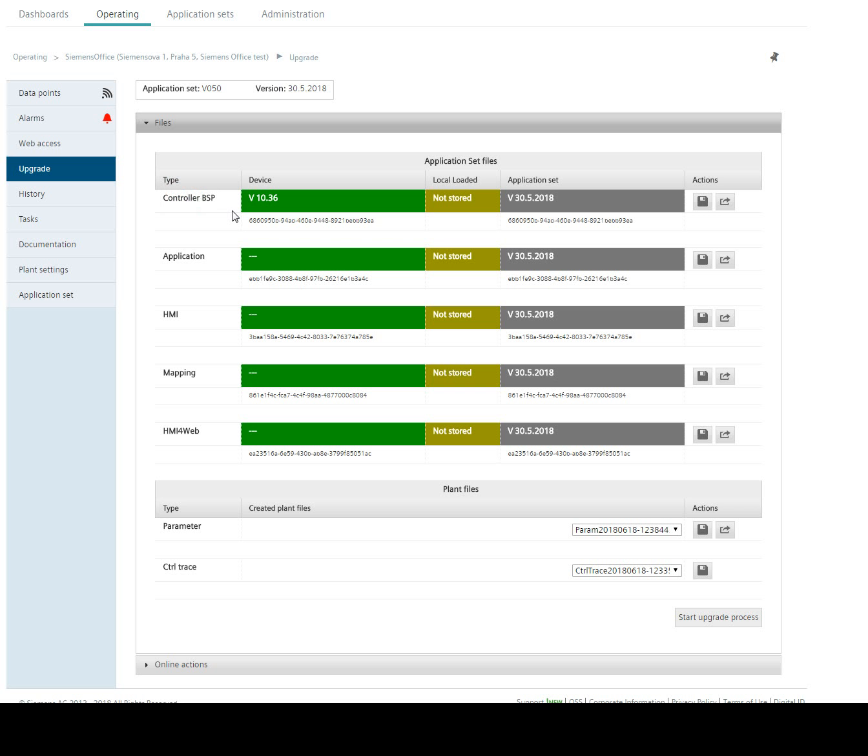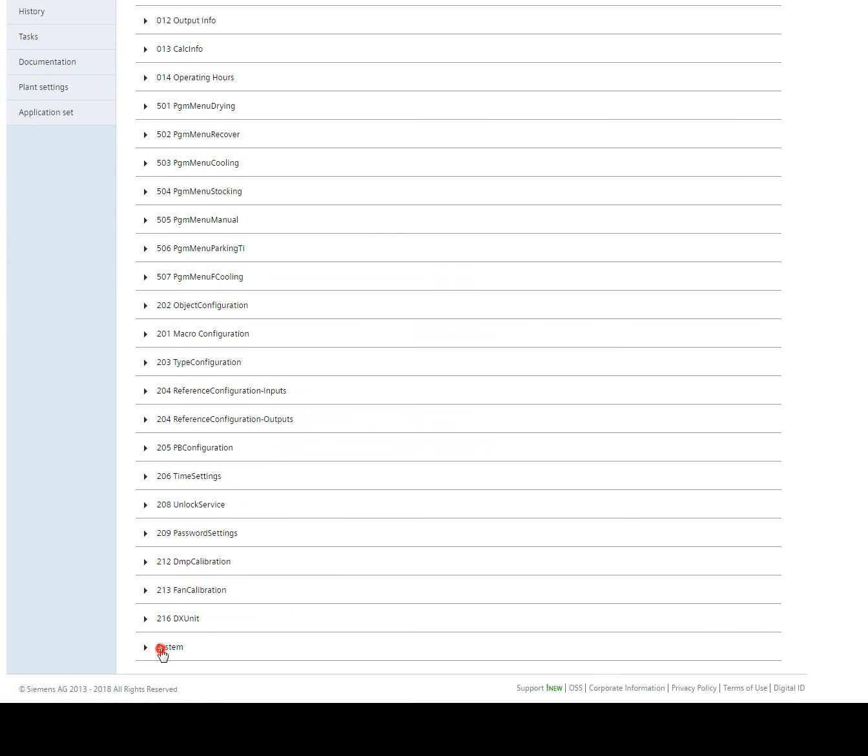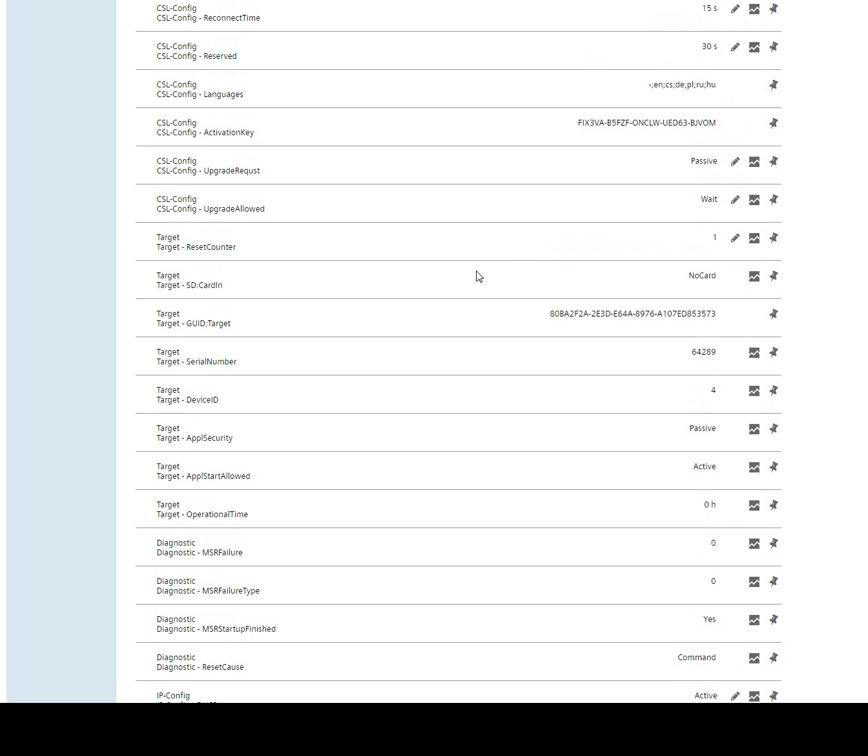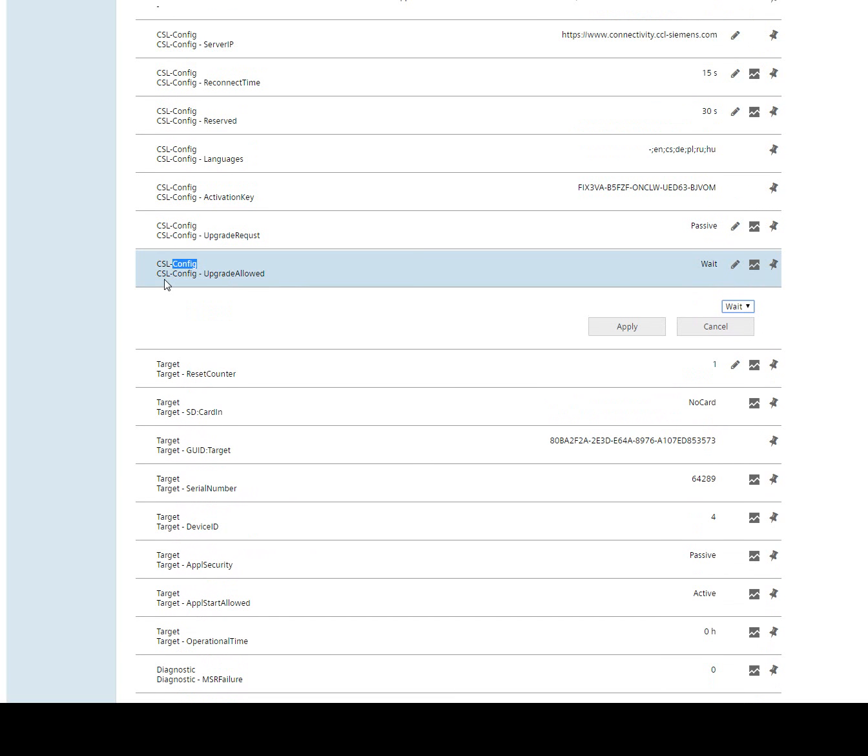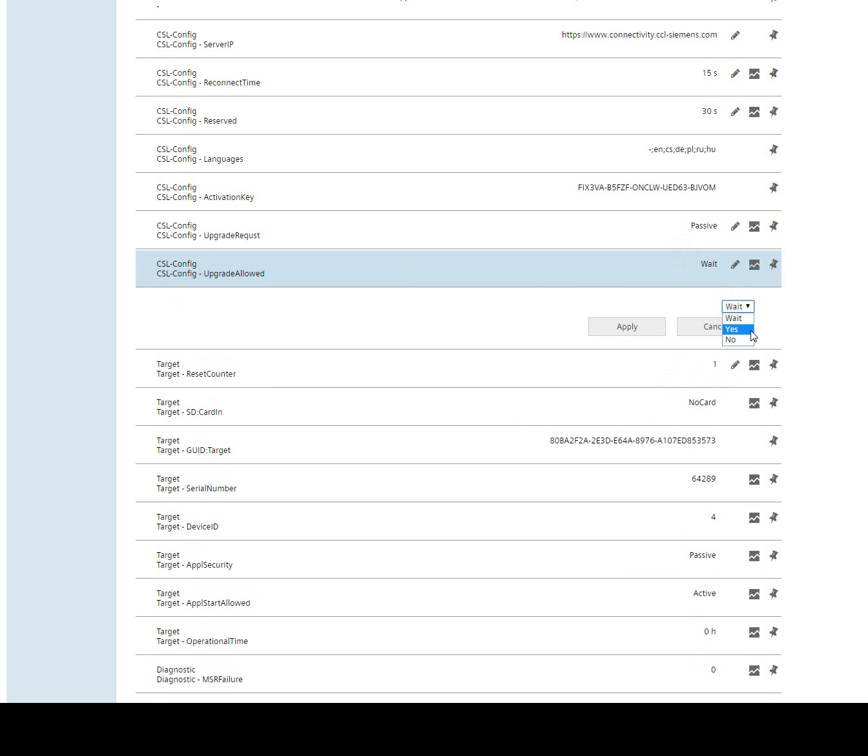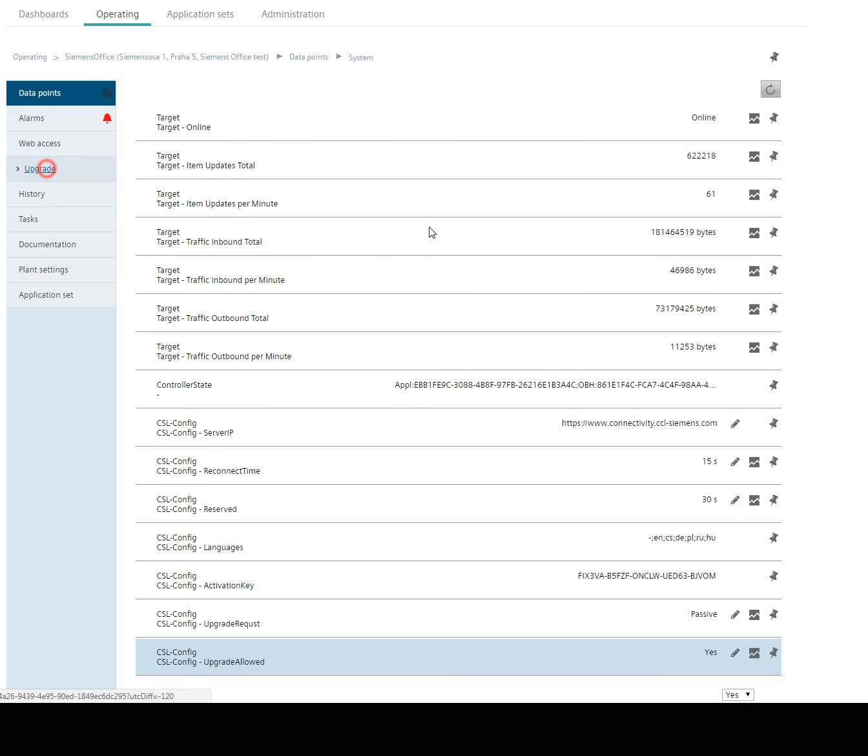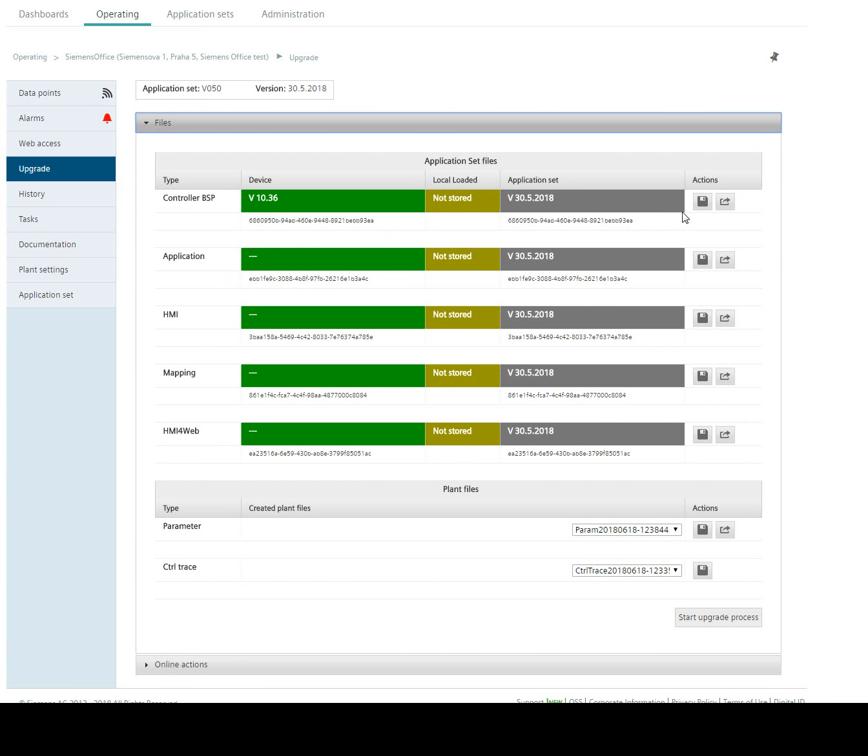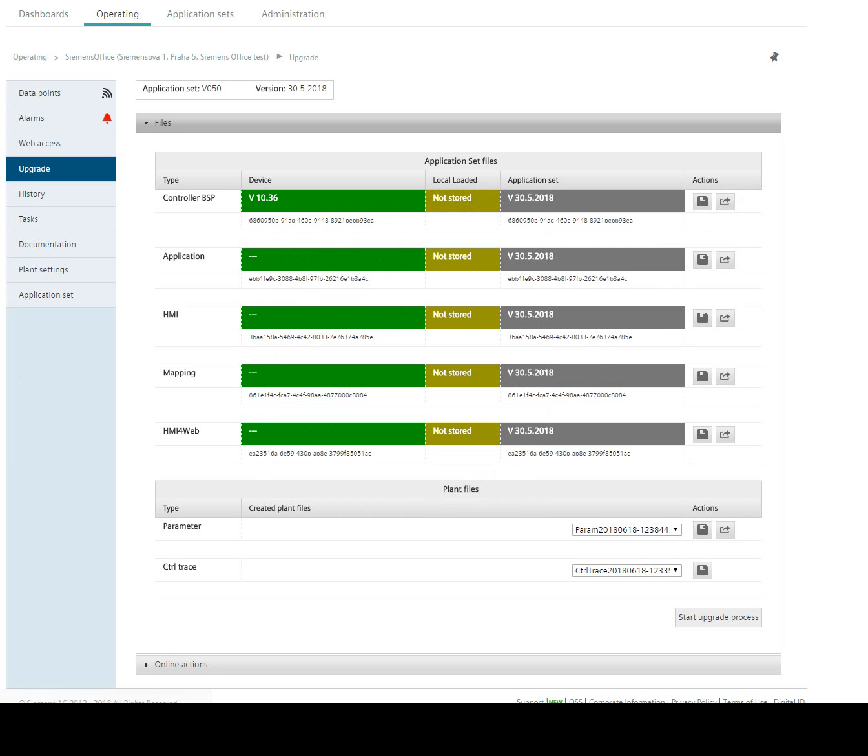There is only one exception and that is controller BSP. In case that we want to upgrade controller BSP, we have to also set up in datapoints in system special flag which says that we are allowed to upgrade the BSP file, the firmware of our Climatix. This file is in system CSL config and we have to change it to upgrade allowed yes. After that we are able to change also the controller BSP or we can use start upgrade process which is used for long term upgrades.